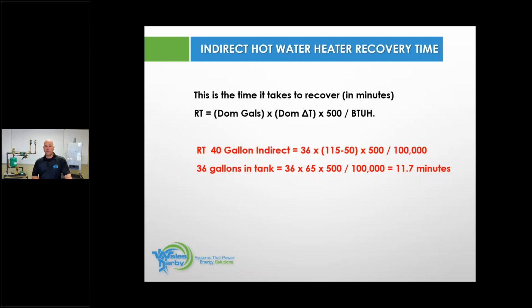Recovery time, 40-gallon indirect. Most tank manufacturers, whether it's a direct fired water heater or an indirect, have the ability to call it a 40, but they only have to adhere to 80% of what they call it. So most 40-gallon indirects actually hold 36 gallons of water.